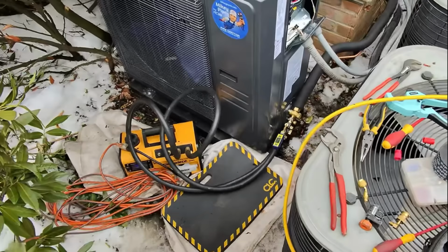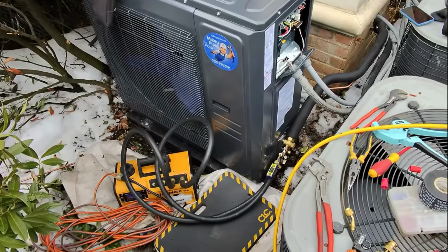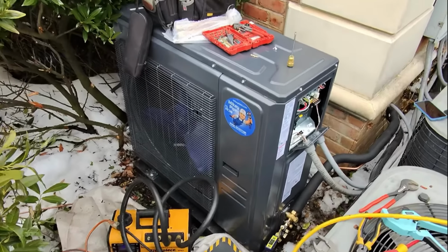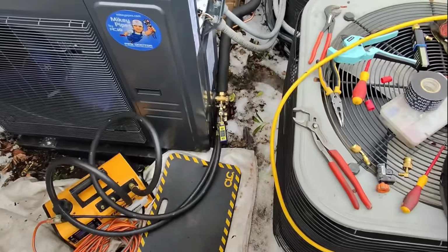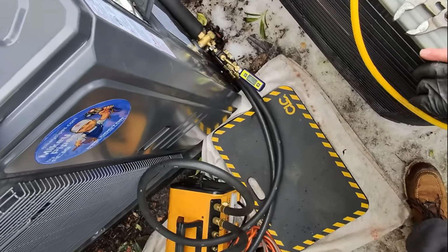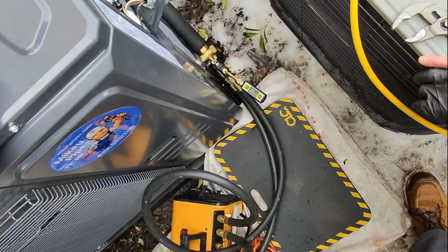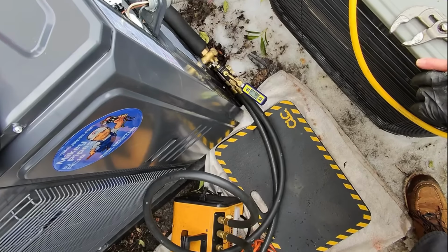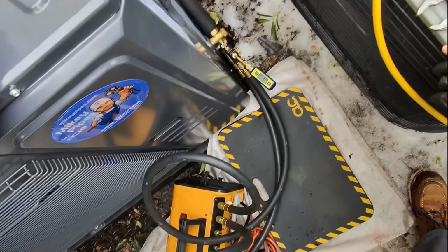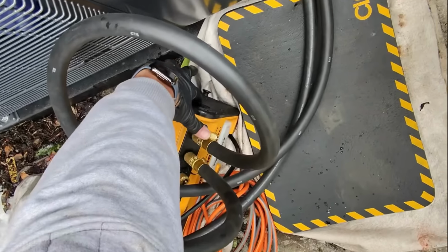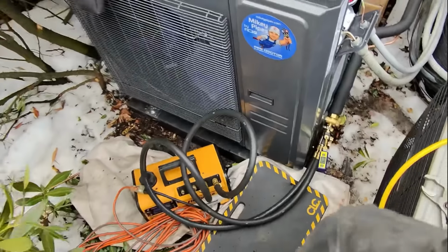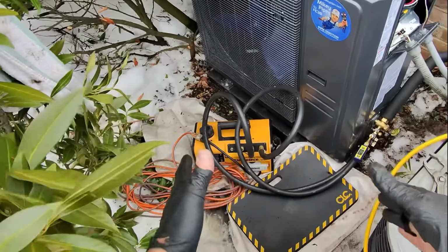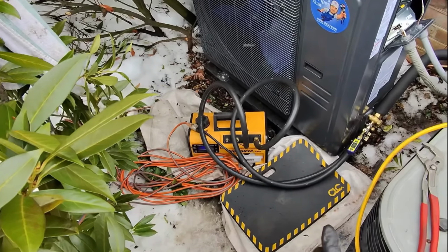Good stuff, so we're going to bring this down as long as possible, as low as possible. We're at 1,000 microns right now, and now we're at 980 and dropping. I'm going to close this ballast, and that's going to allow the vacuum pump to pull an even tighter vacuum.